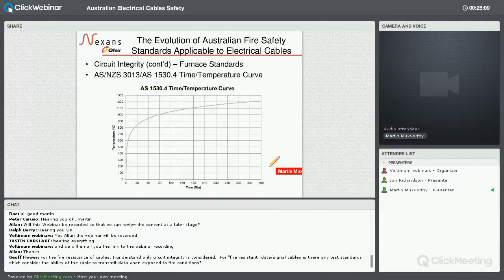I mentioned the time temperature curve. This is what's defined in AS 1530 Part 4. And by no coincidence, it's the same time temperature curve that is used and referenced in the building standards to apply to building materials.